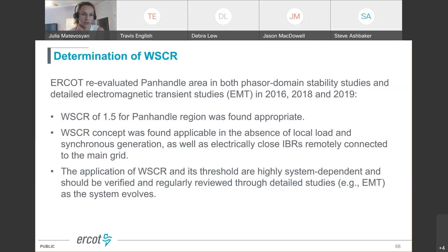For the past 6 years before Lubbock Power and Light interconnected into our system, we used weighted short circuit ratio, maintaining it in real time. We monitor and calculate it in real time and use it as an indicator of how much export can be made from the Panhandle area. The calculation is built into a steady state voltage stability assessment tool that we also use to calculate the export limit from Panhandle, and we recalculate it every 10 minutes based on actual production conditions and grid topology. These two calculations, the voltage stability assessment and short circuit ratio assessment, determine how much output from Panhandle we can handle for the rest of the system.